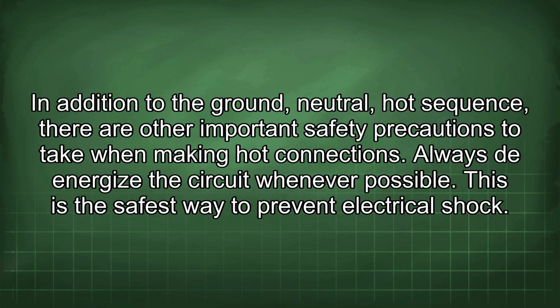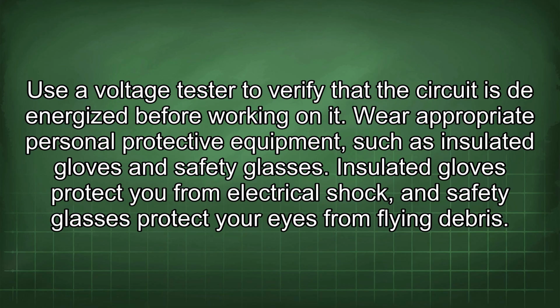In addition to the ground, neutral, hot sequence, there are other important safety precautions to take when making hot connections. Always de-energize the circuit whenever possible. This is the safest way to prevent electrical shock. Use a voltage tester to verify that the circuit is de-energized before working on it. Wear appropriate personal protective equipment, such as insulated gloves and safety glasses. Insulated gloves protect you from electrical shock, and safety glasses protect your eyes from flying debris.